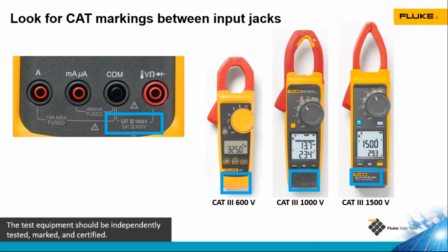Now here's a series of clamp meters. The one on the left is the 325 clamp meter that is category 3 600 volt rated. The one in the middle is the 378 clamp meter that's category 3 1,000 volt rated, and the one on the right is the 393 clamp meter that's category 3 1,500 volt rated. And these pictures are relatively close to scale.